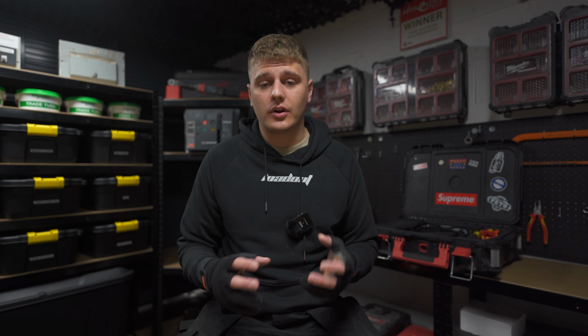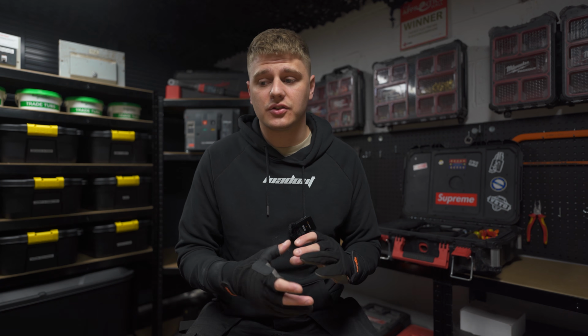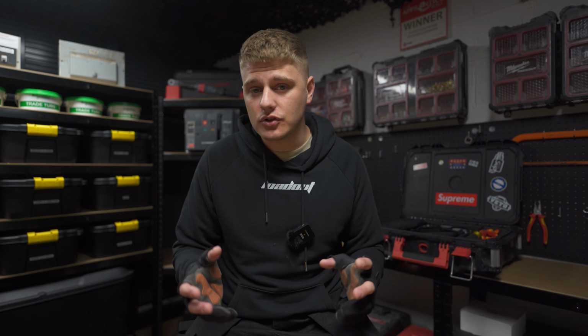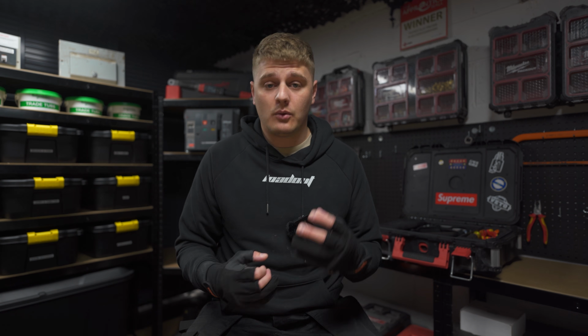So it's important to not only get this right, but also to be aware of previous regulations. The topic of bonding, and specifically supplementary bonding, has changed backwards and forwards so much over different editions of the regulations that there's much confusion on this topic. There's a lot of unnecessary bonds out there, and you just need to be considering this sort of stuff when you're inspecting and testing older installations.